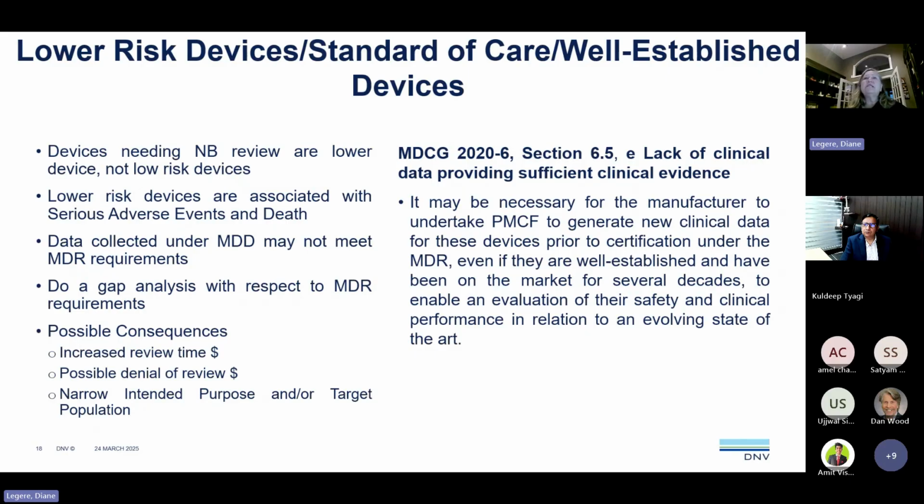So I guess my point is, lower risk devices are still associated with serious adverse events and even death. Data collected under your MDD might not meet the MDR requirements for those reasons I just gave. Do a gap analysis with respect to what the MDR requirements are.